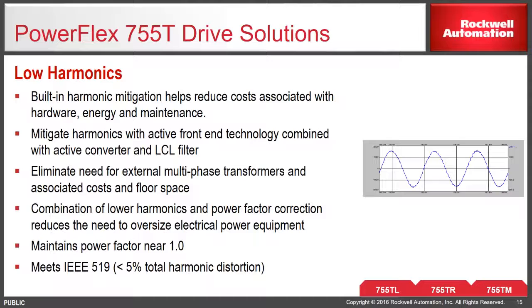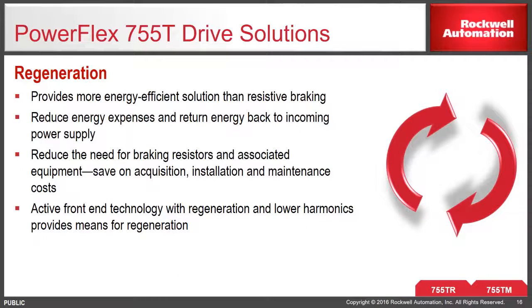PowerFlex 755TR is a regenerative solution. It provides a more energy efficient solution than resistive braking. It reduces energy expenses and returns the energy back to the incoming power supply. It reduces the need for braking resistor and associated hardware. Active front-end technology with regeneration and lower harmonics provides the means for regeneration.